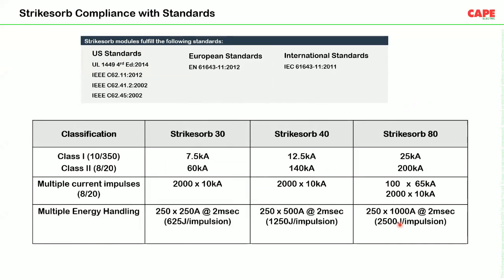Number two, these SPDs are high energy SPDs. Sometimes people say only spark gaps can handle high energy and MOVs cannot, which is wrong. These devices, for example StrikeSorb 80, is a class 1 SPD at 25 kiloampere, and class 2 it can withstand up to 200 kiloampere. These devices are also used for multiple strikes, let's say 100 times 65 kiloampere, 2000 times 10 kiloampere, 250 times the long duration strike, something like that. So StrikeSorb is a very special SPD with a response time of less than 1 nanosecond, very expensive, but for very specific and very big applications.